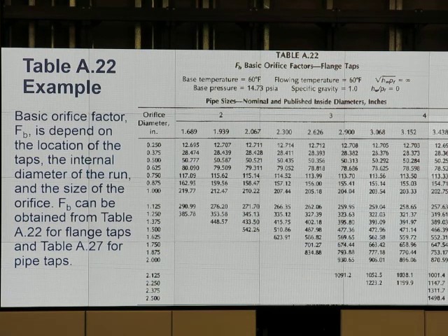So as an operator, would you necessarily be on the hook for changing the orifice plate in the midstream meter? No. I'm not going to change the plate on the midstream company's meter. Okay, well, how do you make sure that the plate is working properly in their meter? You're going to have to witness it when they calibrate it. Whenever the pipeline company calibrates it, you need to be there and witness it.